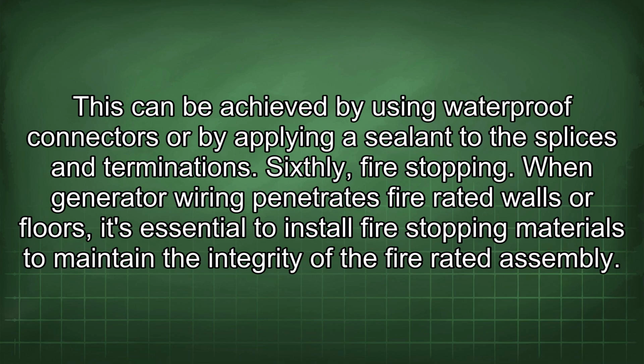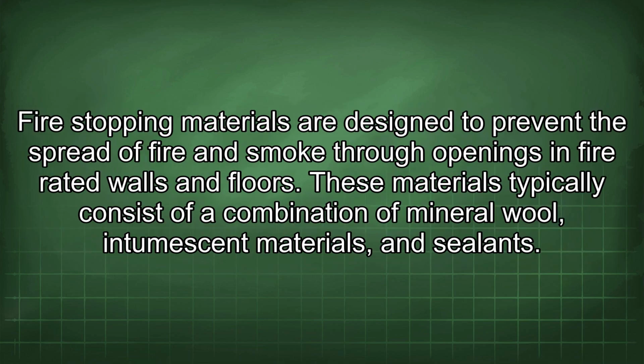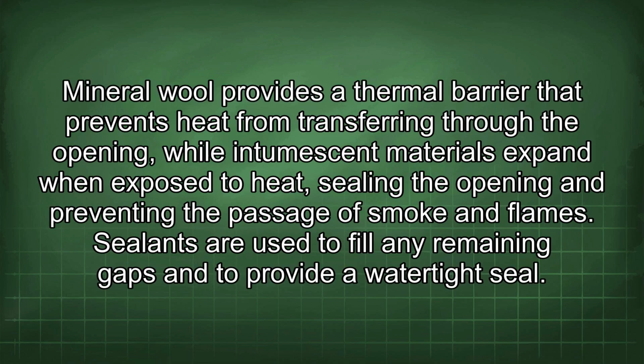Sixthly, fire stopping. When generator wiring penetrates fire-rated walls or floors, it's essential to install fire-stopping materials to maintain the integrity of the fire-rated assembly. Fire-stopping materials are designed to prevent the spread of fire and smoke through openings in fire-rated walls and floors. These materials typically consist of a combination of mineral wool, intumescent materials, and sealants. Mineral wool provides a thermal barrier that prevents heat from transferring through the opening, while intumescent materials expand when exposed to heat, sealing the opening and preventing the passage of smoke and flames. Sealants are used to fill any remaining gaps and to provide a watertight seal.